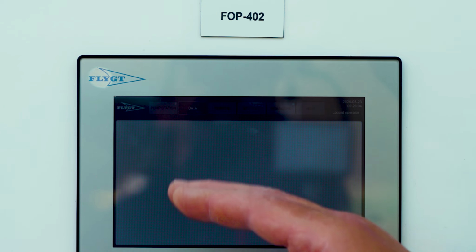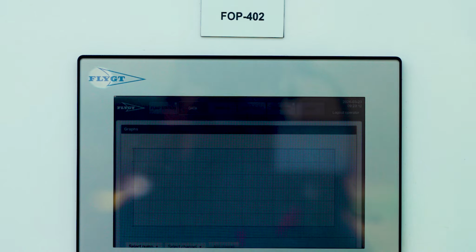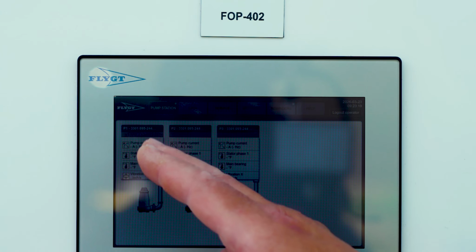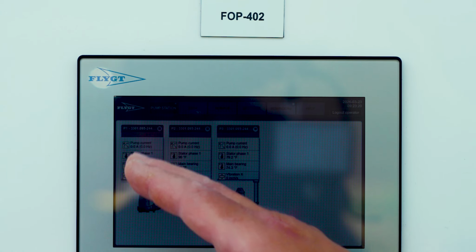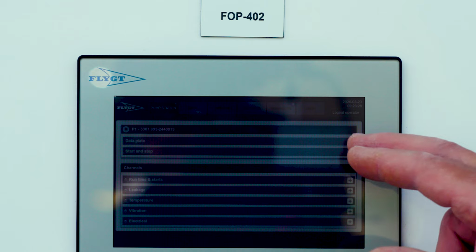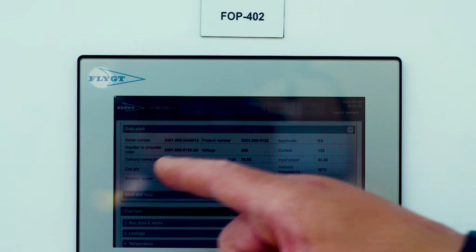The next screen is the data button. Here you can look at graphs, and you can select a particular item, or you can go back to the status page and click on that item and pull up the graph from there, and I'll demonstrate that. So if I go to the status screen and I click on any one of these pumps, I've got pump 1, and it has the data plate information. So the same information that was on that data plate we looked at when the pump was pulled is displayed here. And then it also has the start and stop log. So you can see all the starts and stops, how long it ran. And I'm going to close these as I go so it doesn't get too busy.